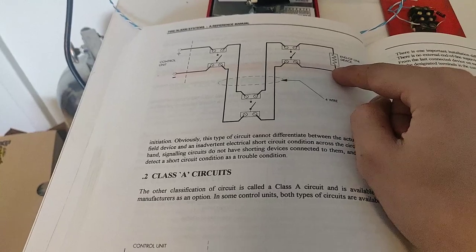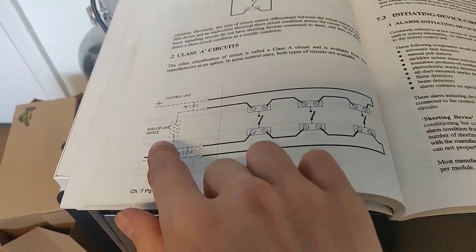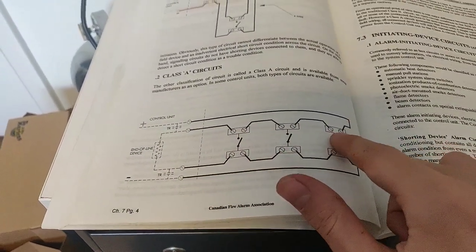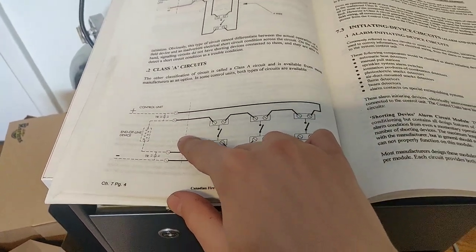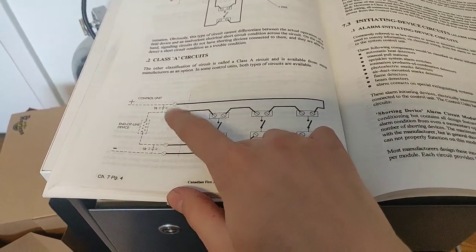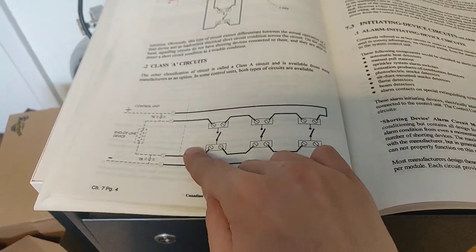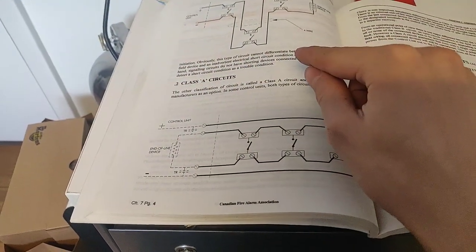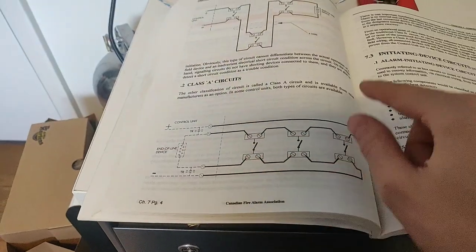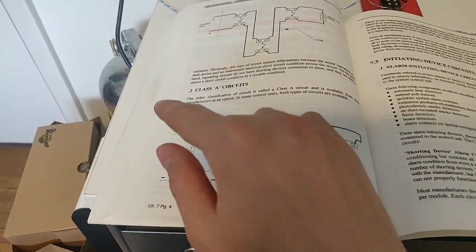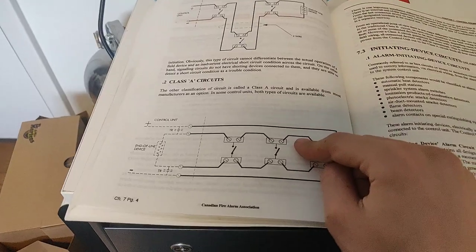So the class B system: from the panel, we go through our initiating devices and to our end of line resistor. Whereas with class A, it goes through our initiating devices and then back to the panel. Now one common confusion here, or mistake, is that you need to ensure that this wire is in a separate conduit. So I couldn't have one conduit from the panel to my pull station and then back in the same conduit. The wire has to return in another conduit. So keep that in mind or you will fail inspection.